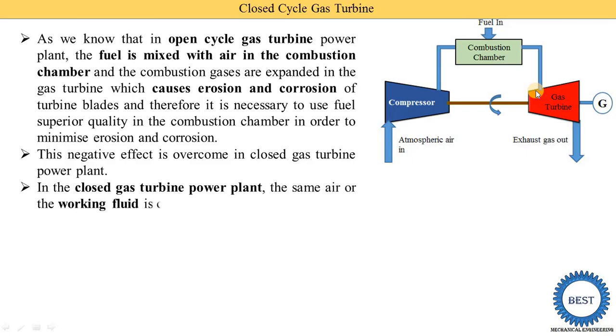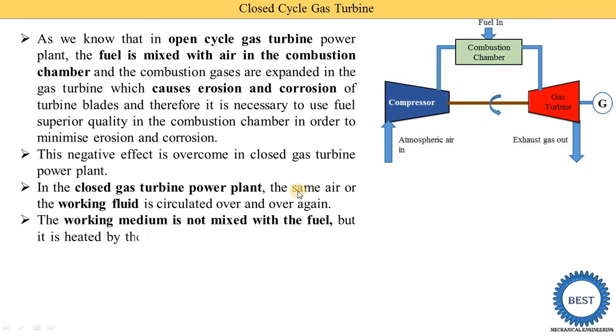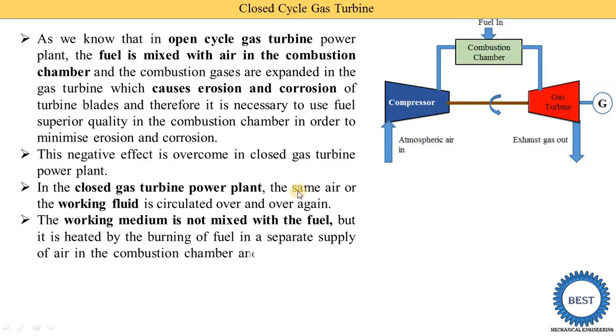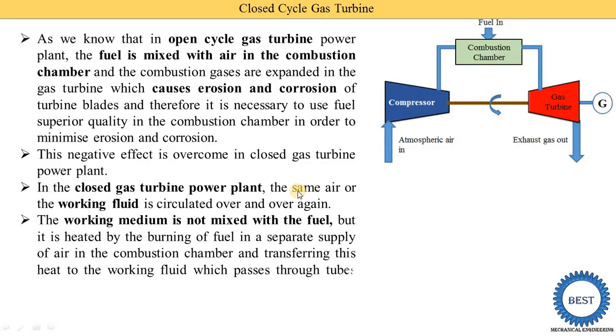In a closed cycle gas turbine power plant, the same air or working fluid is circulated over and over again. The combustion product is not circulated in the full system — only the working fluid. The working fluid may be air, helium, argon, or some other working fluid. Combustion product is not circulated through all the components; only the working fluid is circulated. Due to that, erosion and corrosion chances are reduced in the turbine in a closed cycle power plant.